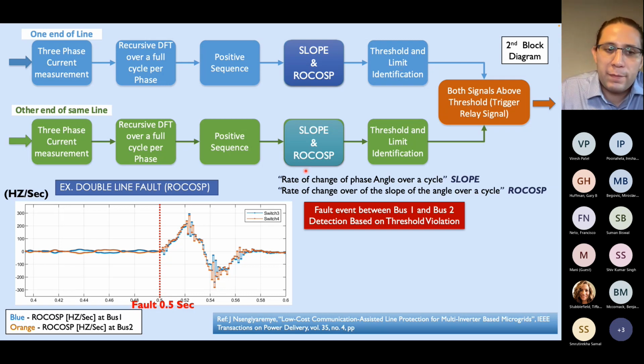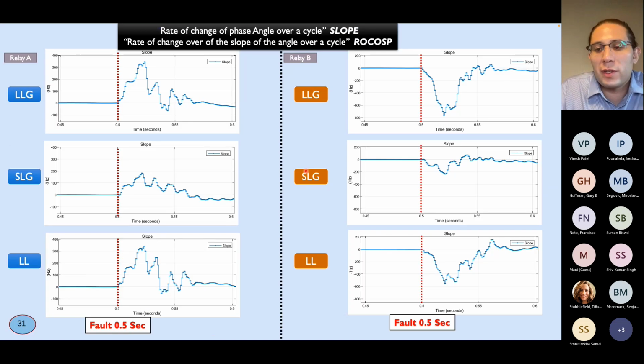fault. In the following slide, I'm showing the different types of cases, which are line-to-line ground, single line-to-ground, and double line-to-ground, as seen from different ends of the relays. As we can see, the fault can be identified by the slope method, and also for the single line-to-ground fault. Usually we use a threshold here, and the threshold we utilize is the frequency of the grid. As we can see, all of them pass the threshold.